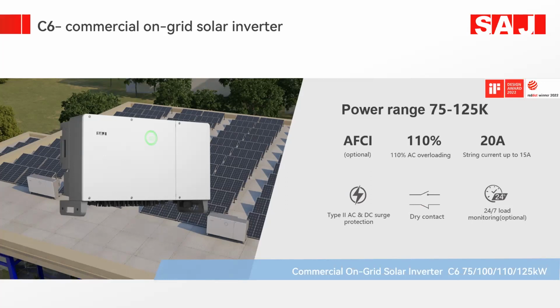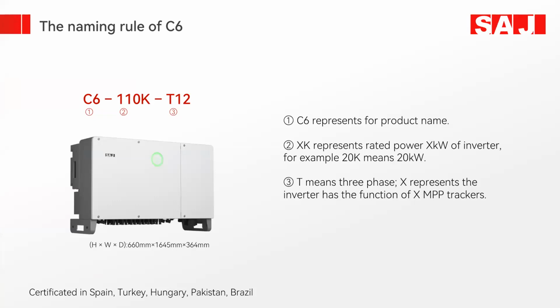The commercial series on-grid inverter power range starts from 75 to 125 kilowatt. AFCI is optional. 110% AC overloading, 20A string current, and type 2 AC/DC surge protection. Dry contact and 24/7 load monitoring are optional. The naming rule of C6 is the same as the R6 series. C6 represents the product name, XK represents the rated power, X kilowatt of the inverter. For example, 20K means 20 kilowatt, T means three phase, X represents the inverter has X MPPT trackers. Our C6 series is certified in the Spain, Turkey, Hungary, Pakistan, and Brazil markets.